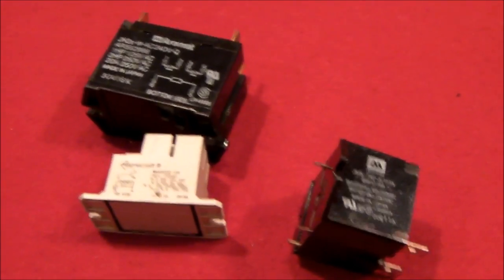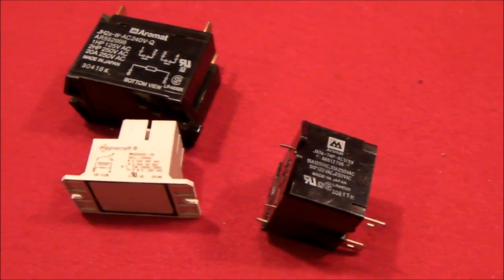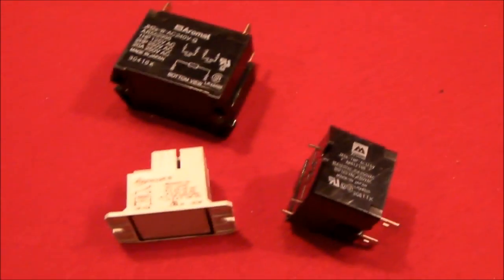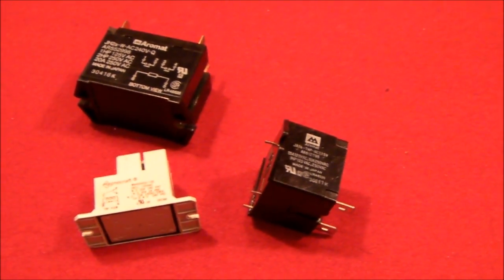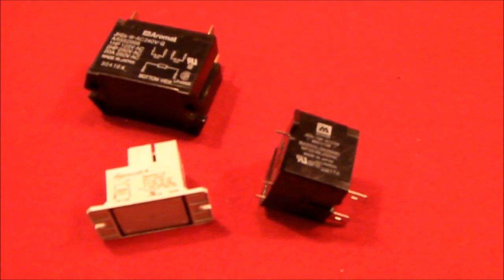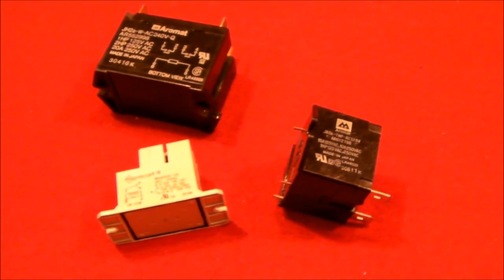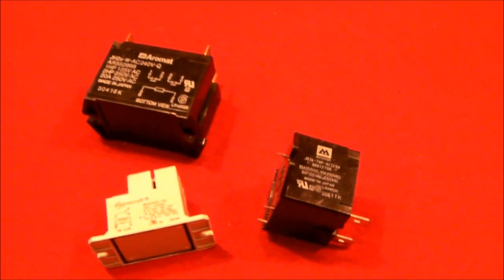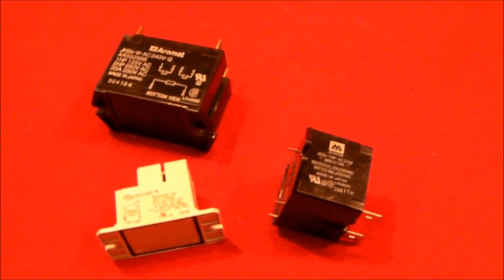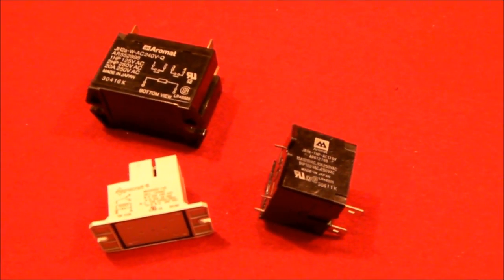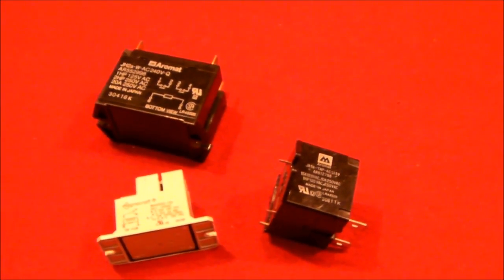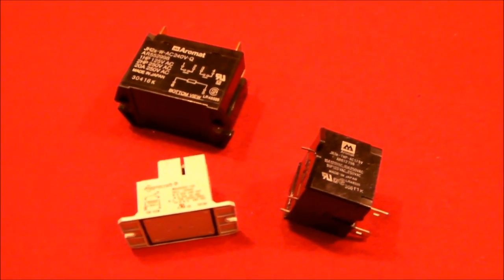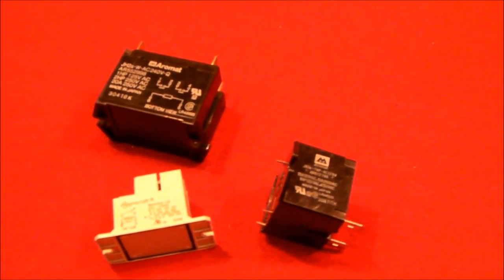Two bits of information would be one, the AC coil on the relay or the contactor should be 120 volt AC. And I would recommend against using solid state relays. They're awfully cheap. You can buy them from Asia for three or four bucks, a 40 amp solid state relay with a 120 volt control circuit. And it will handle a substantial amount of inrush for a very short period of time. Since solid state relays are generally not motor rated, and you don't know really how long it's taking your pump to start, I would recommend against solid state relays.